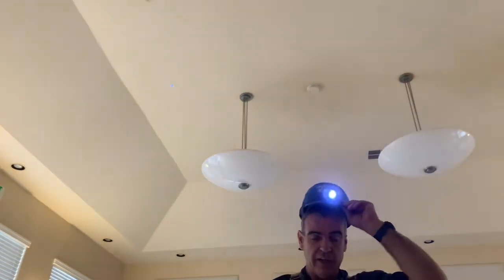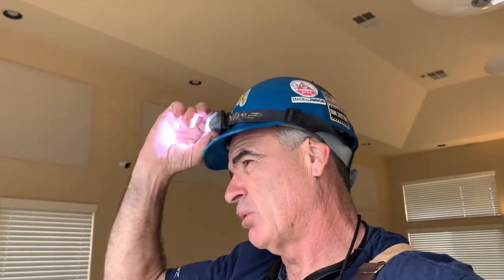Whew. All right, well, as always, I want to thank you for coming along with me on these heads over 20 years old changing out adventures. Yeah, if your quick response fire sprinklers are over 20 years, either get them tested or change them out. And if you have 15 heads, I guess it's easier to change them out than to test four of them. So a small job, I guess that's what we do here.